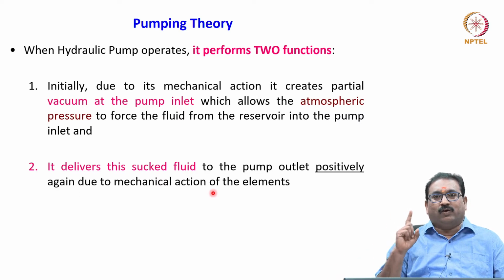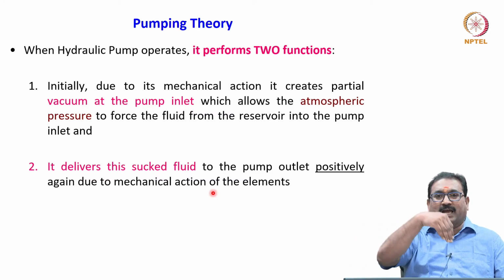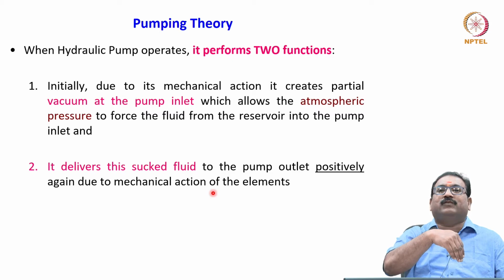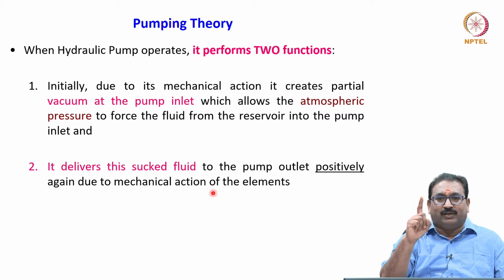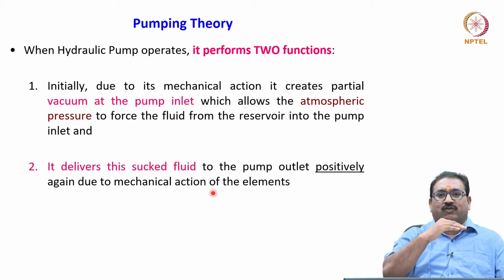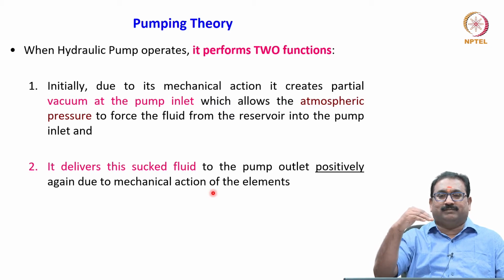This creating of the vacuum always happens at the inlet. Then, due to the differential pressure, the tank is always kept at atmospheric pressure. That is why air breathers are there. On the tank surface, air is always acting. Due to this differential pressure, meaning the partial vacuum created at the inlet and the tank pressure of 1 bar, it will suck the fluid. Once it catches, the fluid will be transported.